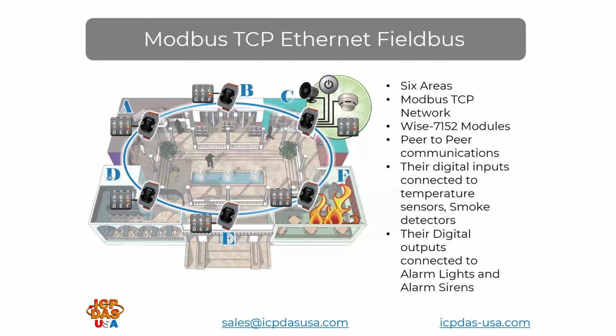Looking at the image, when a fire is detected in Region F, the WISE 7152 module in Region F transmits an alarm via its advanced peer-to-peer function. All warning lights and alarms represented in Region F on the 6 WISE 7152 modules distributed in the 6 regions will be turned on to indicate a fire is occurring in Region F. Knowing the exact location of the fire can help guide personnel to a safe exit path so as to avoid the fire. After the fire in Region F has been put out, you just need to press the emergency switch to turn off the alarm.